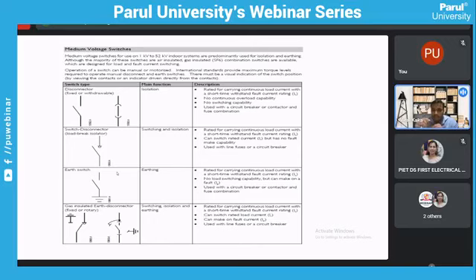So in normal practice, if we are seeing a secondary switchgear, it will be a bus bar and then line, and then a breaker, and then a 3-position disconnector switch which will be connected towards the cable. But this arrangement of bus bar and the 3-position switch is reversed in a primary gas insulated switchgear. And the earthing operations are being performed by the breaker. In that case, you need to first of all keep the 3-position disconnector switch to earth, and then you need to switch on the CB to earth your cable. But that is the practice in a primary switchgear.